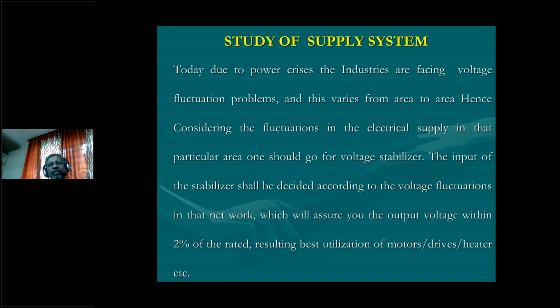Now consider that there is a supply break, failure of supply, and the DG starts automatically and changeover occurs. Now when changeover occurs, your supply will be restored at 415 volts. The stabilizer will take some time to stabilize that voltage because the servo motor will sense, it will move, it will reduce the voltage, but it will take time. But in the meantime, at 415 volts, your servo stabilizer will give an output of 35 volts plus. So initially you may get 450 volts. This is in the case of a generator.